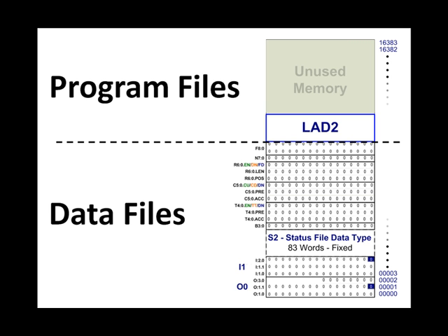You can expand, contract, and create new data table files offline only. You can edit the logic online, but not create a new program file online. With the newest family of processors, not covered in this presentation, you can do almost anything online and in the run mode.